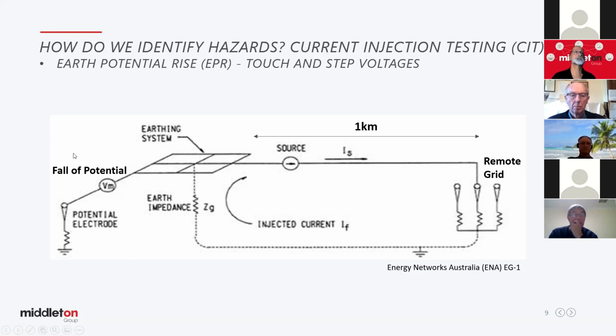Now, how we measure that is we do a fall of potential run, sometimes called an EPR run, or a potential rise run, where we might go out up to a kilometre again from the substation. We take a reference lead that's connected to the substation, and we measure the voltage of the soil with respect to the zone substation, and we get ourselves a curve. When we go out far enough and that curve flattens out, we're coming towards the measurement of what the maximum earth potential rise is for that zone substation, for that generated current.